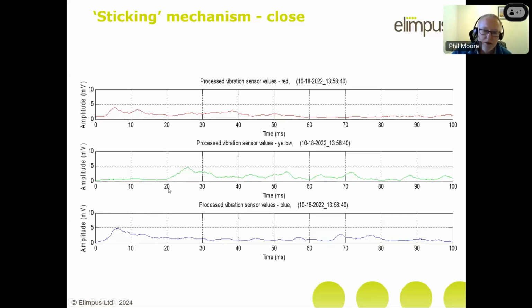And when this was investigated, this is a breaker with a hydraulic mech. It was discovered that hydraulic oil had actually got onto the actuator, and it was slowing the actuator as it tried to start moving the contacts. And once that was cleaned up, we tested it again, and this yellow signal then behaved similarly to the red and the blue.